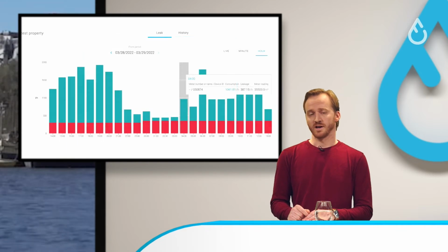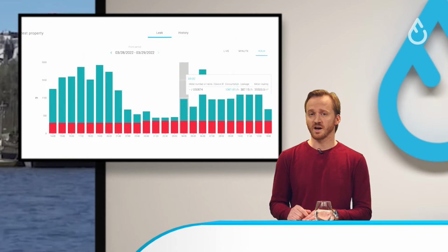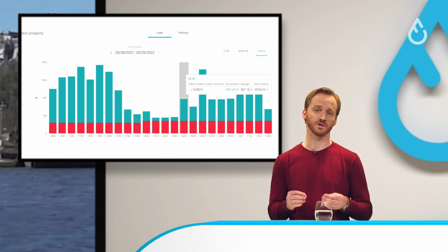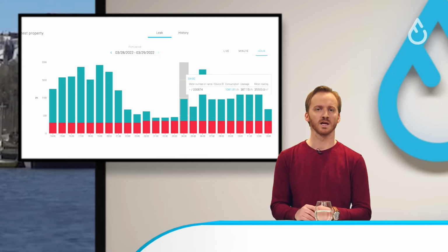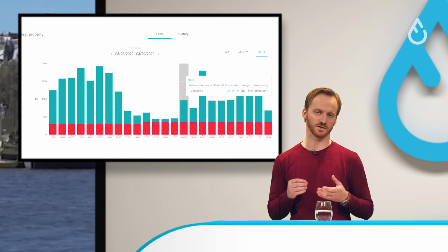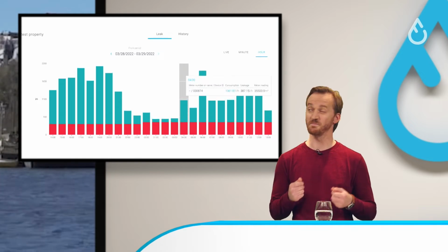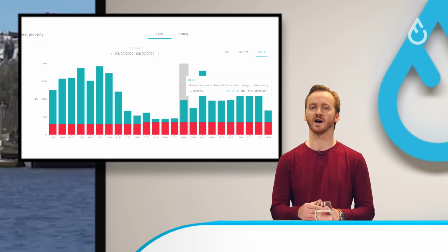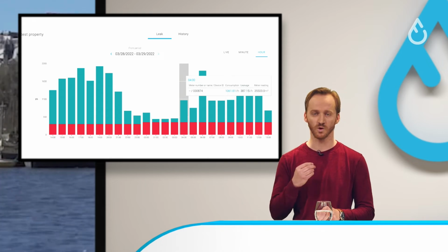The leak is found at night, in this case between midnight and 6 a.m. The system registers there's water consumption every minute. If that's the case, then we're certain there's a leak. Because based on our customer data, we know that even in the busiest hotel or apartment building, consumption should go down to 0.0 multiple times a night.